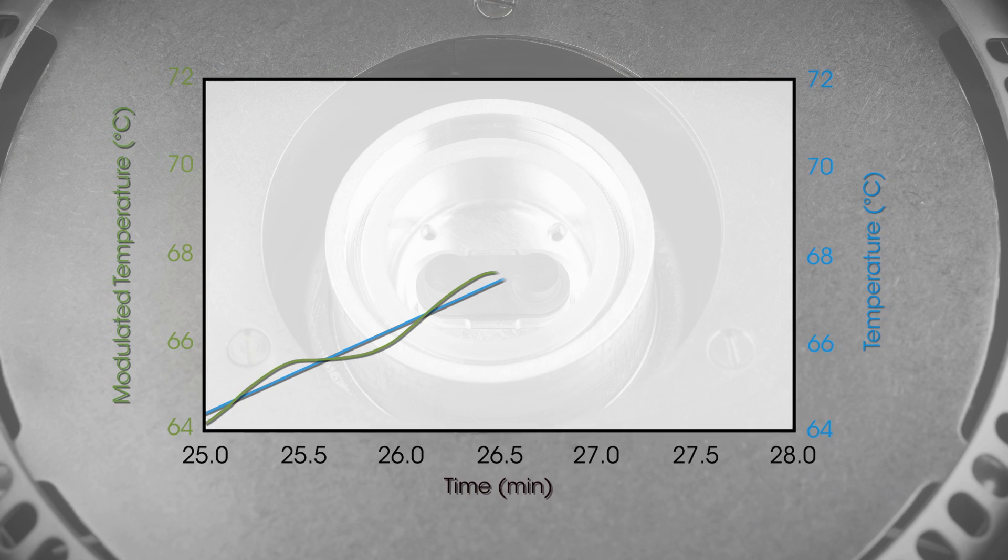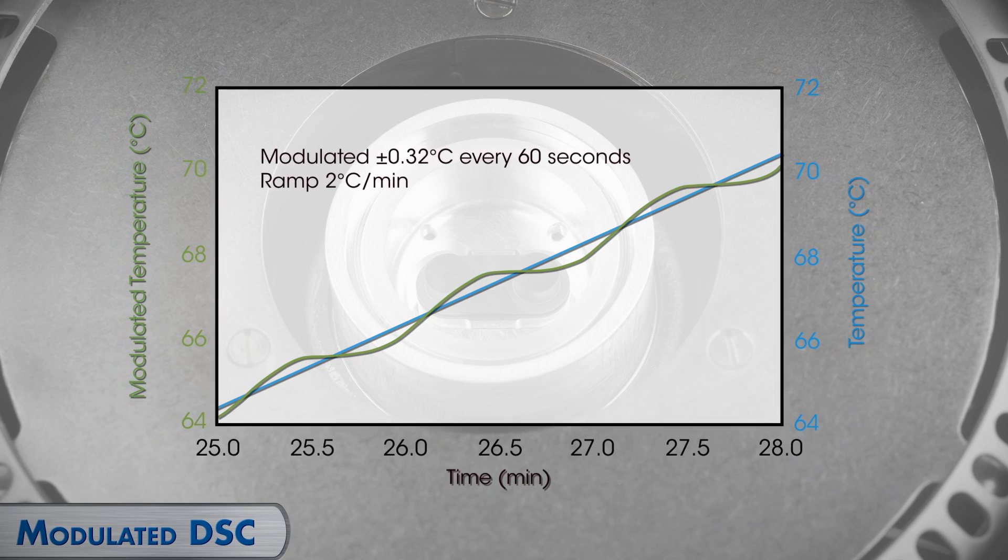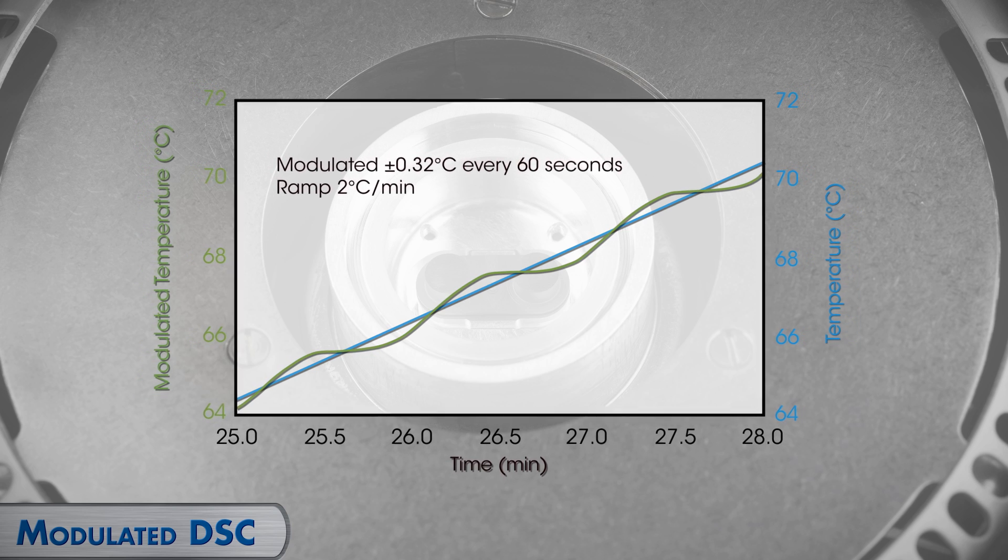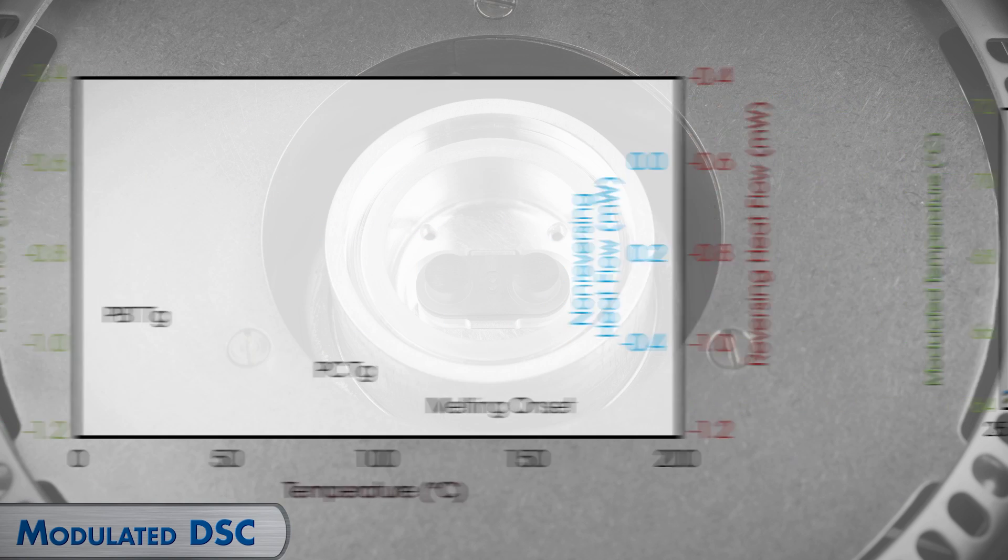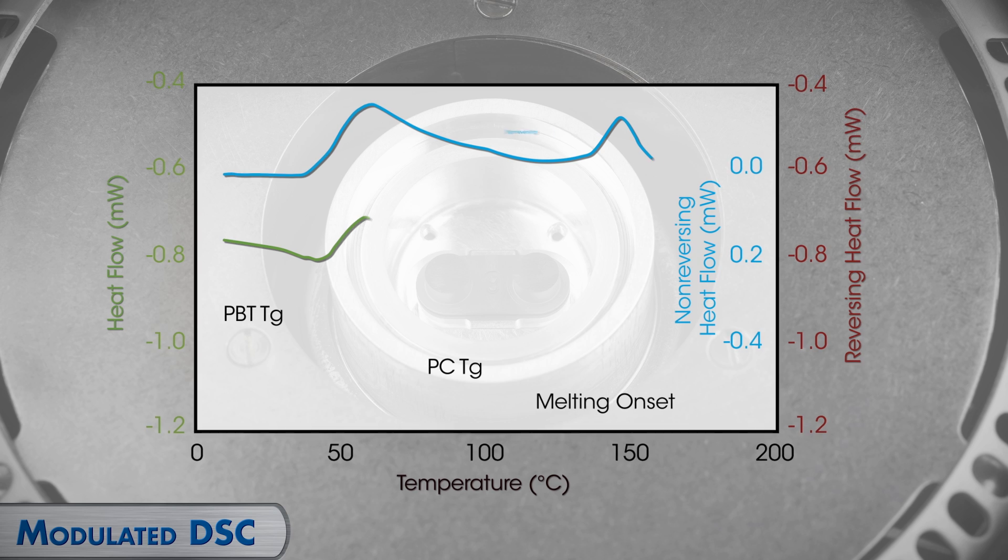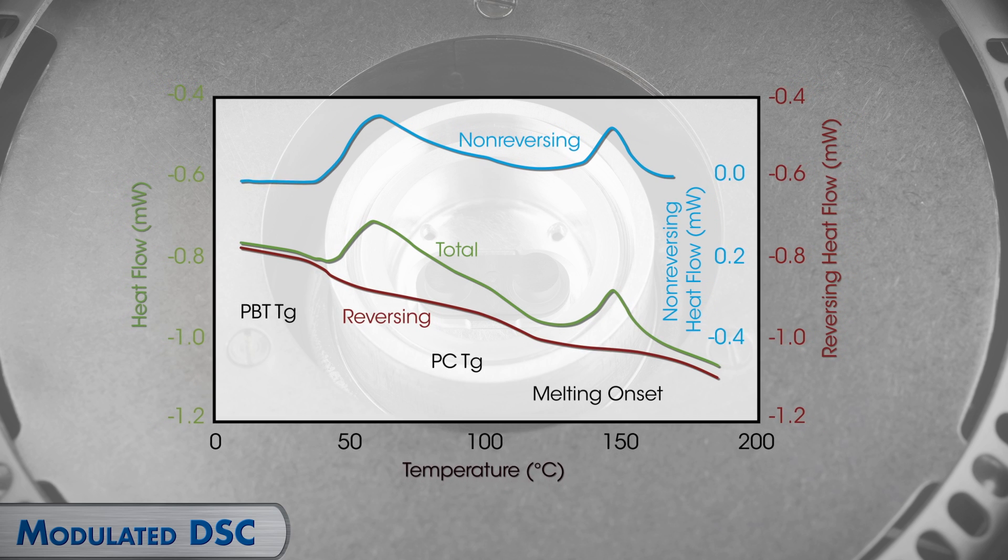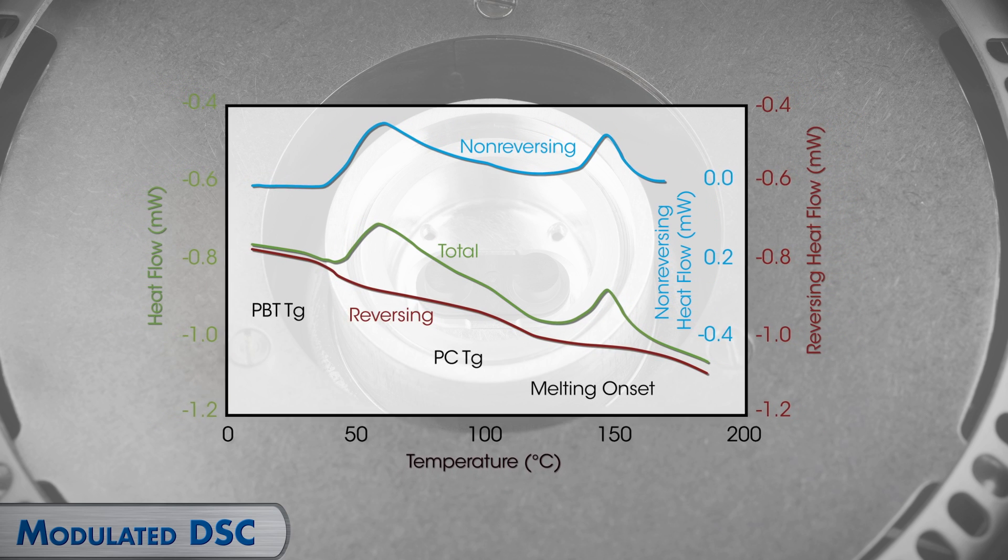TA's patented Tzero modulated DSC technology is now standard on all new Discovery DSCs, providing users with the ability to separate heat capacity events from kinetic events, allowing for a more complete understanding of material properties.